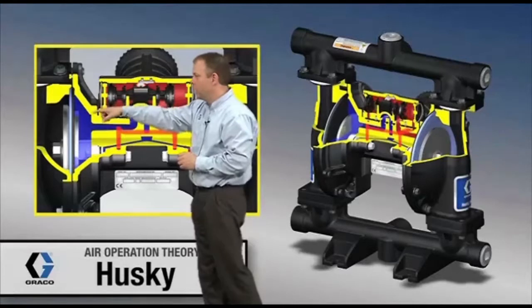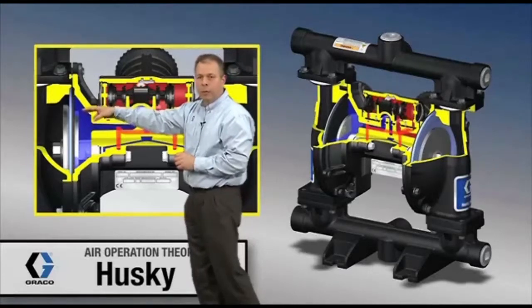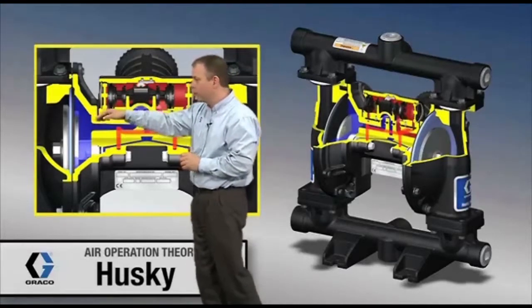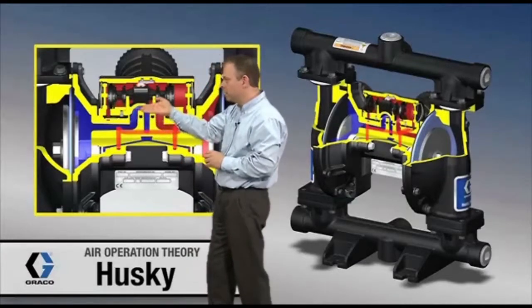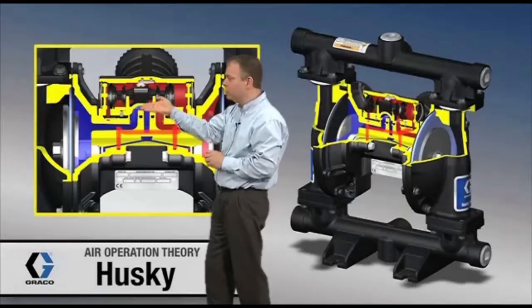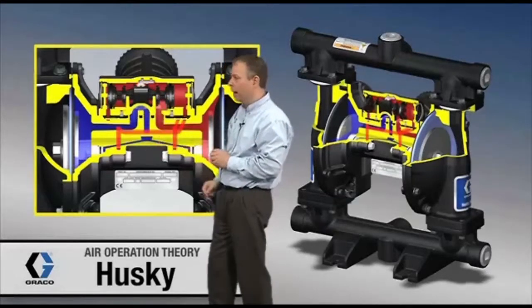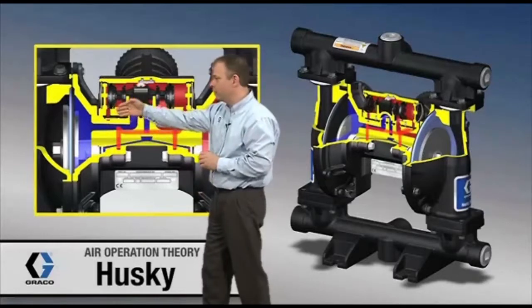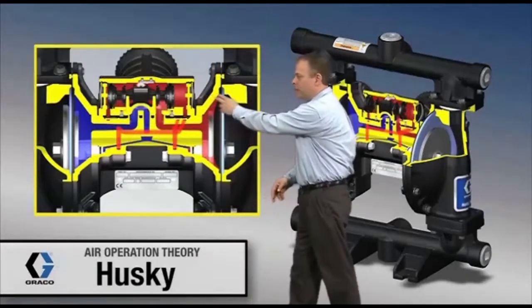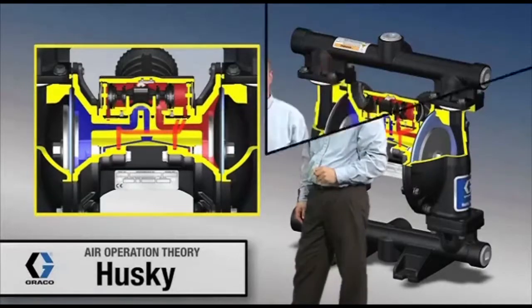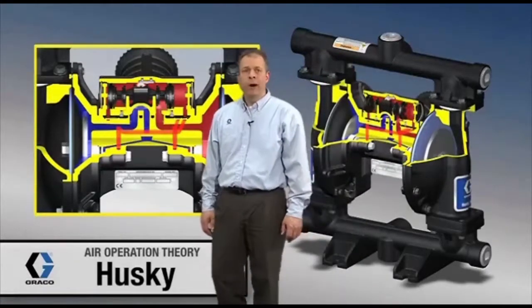Over on the other diaphragm we've got blue again — that's reduced air pressure or exhausting. It's connected through here and coming up through a passage with a cup and plate up in this module, connecting it to a vent. So we've got vent over here and high pressure from the air valve going to this diaphragm.